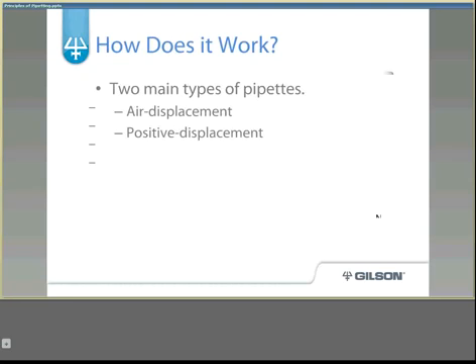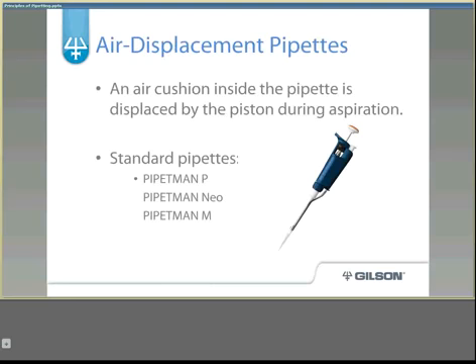There are two main types of pipettes: air displacement and positive displacement, and they function very differently. Air displacement pipettes have an air cushion inside the pipette that is displaced by the piston during aspiration, meaning the volume of air displaced is equivalent to the volume of liquid aspirated. Examples include the Pipetman P, Pipetman Neo, and the Pipetman M.